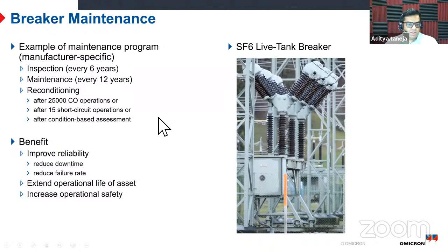Other thing, while doing the maintenance, we generally do the inspection test every 6 years. This is not only the visual inspection. Visual inspection is done every year, but this is inspection without opening any circuits, without doing any changes in the breaker condition when it is in operation. We try to do some tests to know the health, and this is what my focus is today. This is where we want to do non-invasive measurement. We don't want to change any connection or open any circuit to know the health.